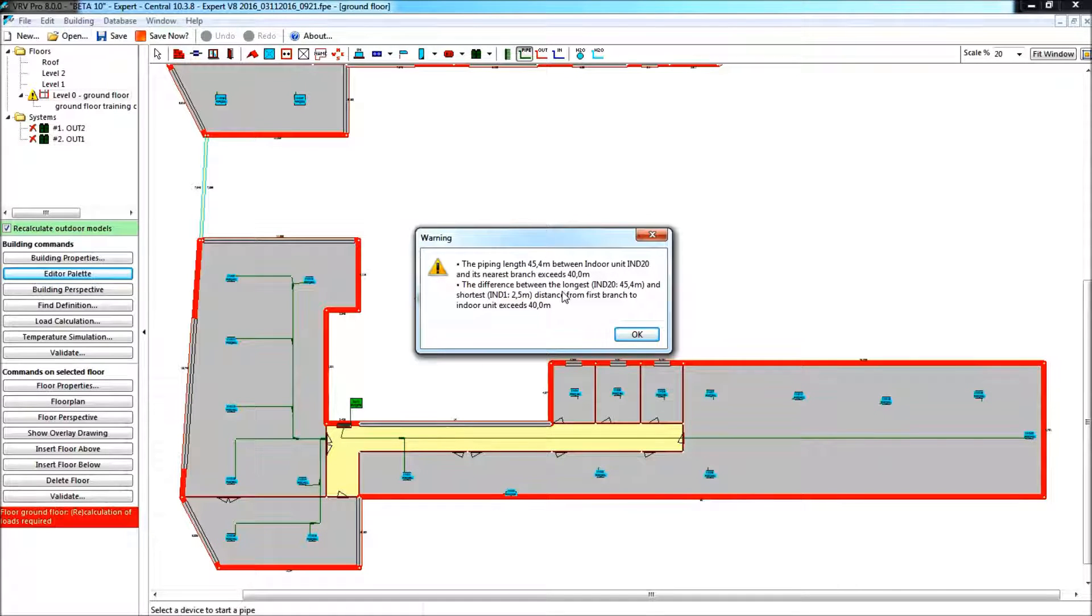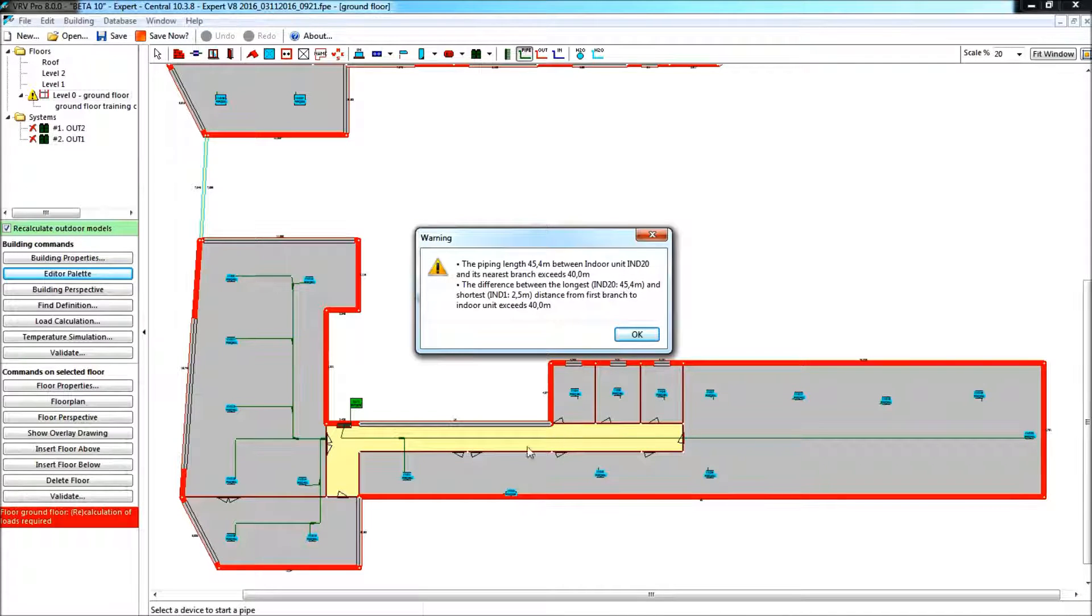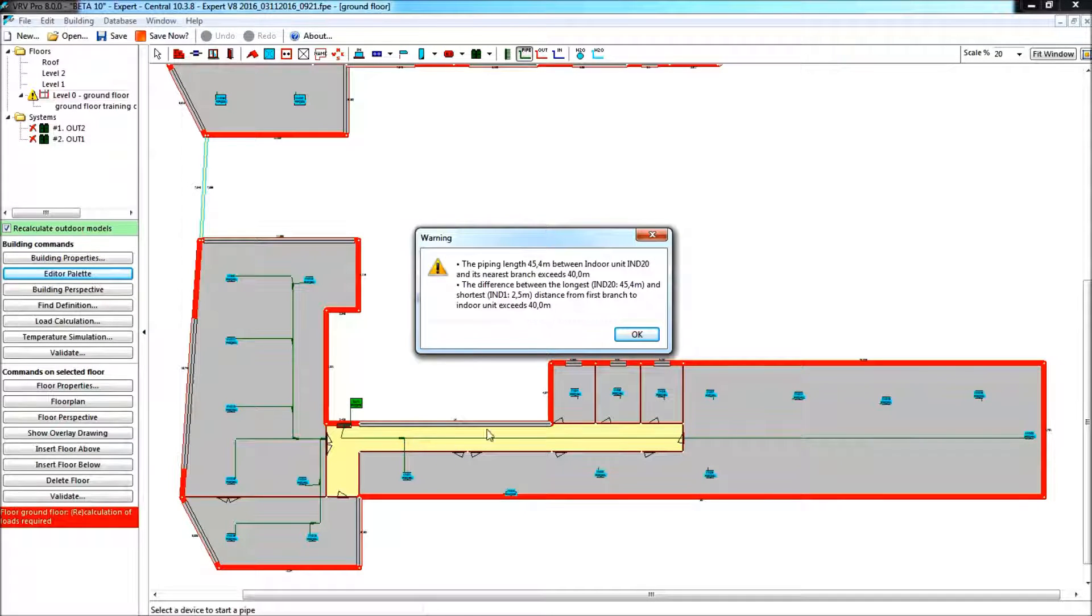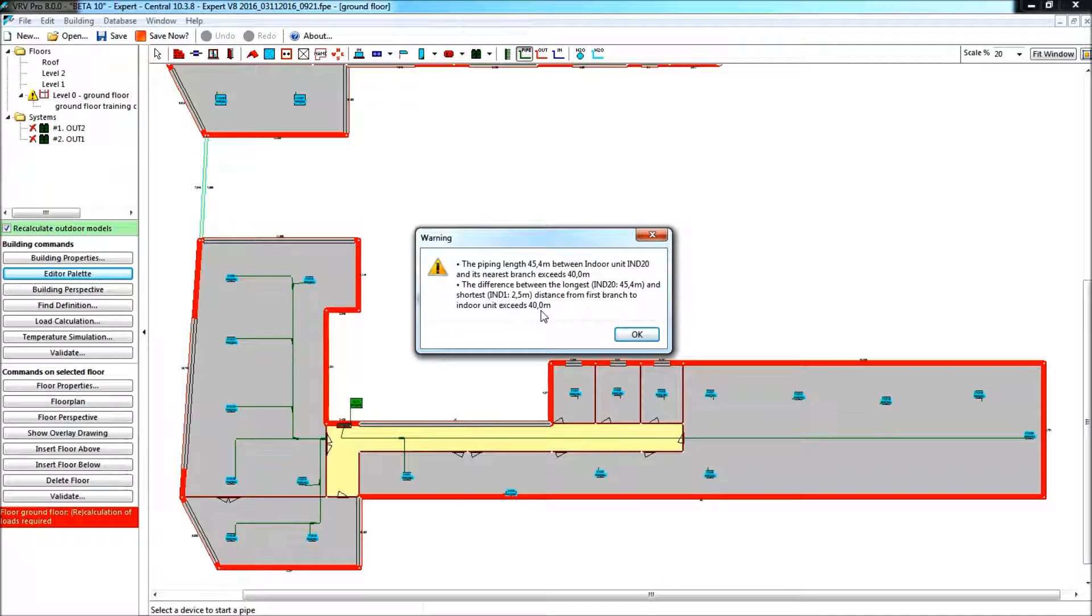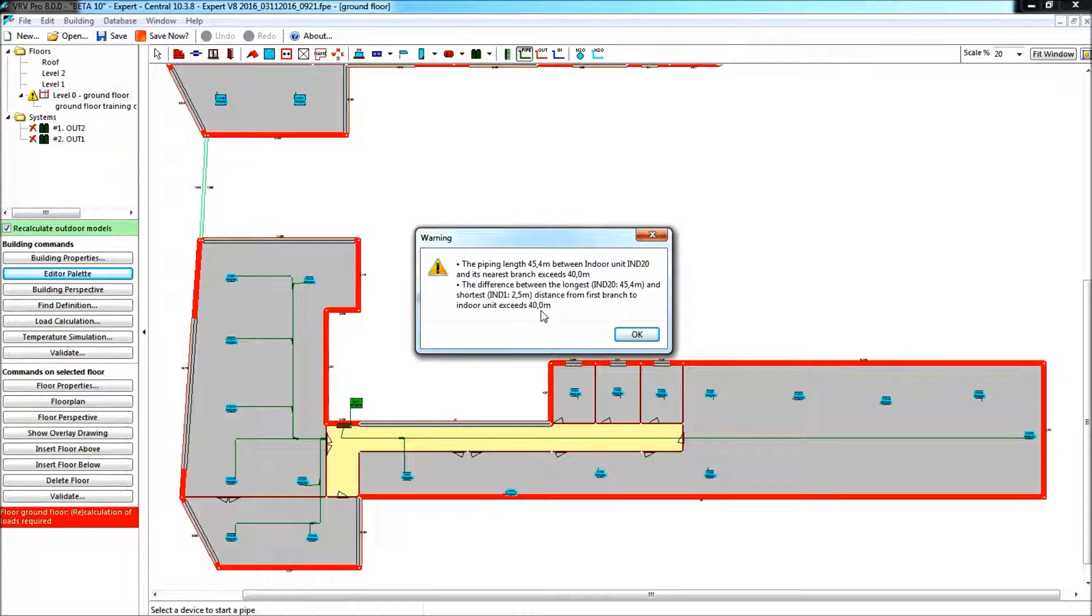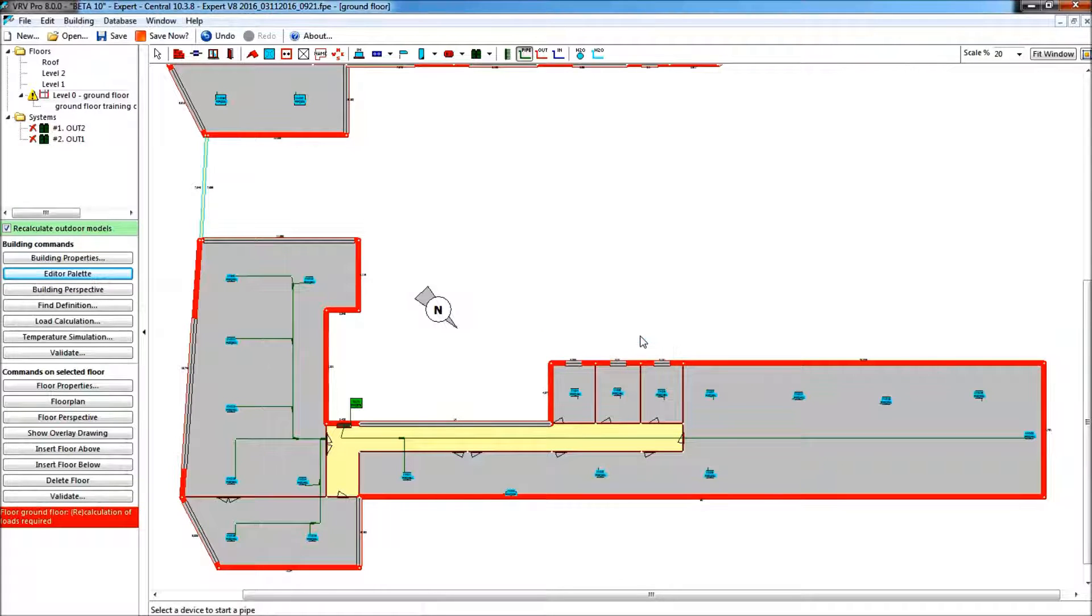But then the second rule, the golden rule, longest minus shortest, the longest is 45.4, that is that stretch, and the shortest is 2.5 meters. Well, the difference cannot be more than 40 meters. It can, but then it will have some consequences, that we will have to resize the intermediate piping. This is an interesting information.